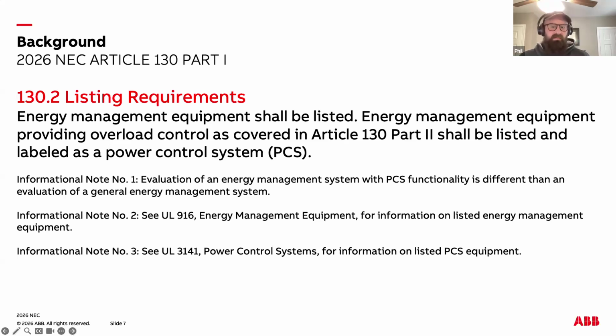Because at the time of the release of the 2026 code cycle, UL 3141 is still in outline of investigation draft form, I would encourage anyone installing PCSs in jurisdictions enforcing the 26 cycle to appeal for an interpretive exemption under NEC 90.4. There are several companies claiming UL certification, but to date, there are extremely few products that are actually listed to UL 3141 because of its draft status. So this is one of the instances where the code is actually a bit out in front of the industry.